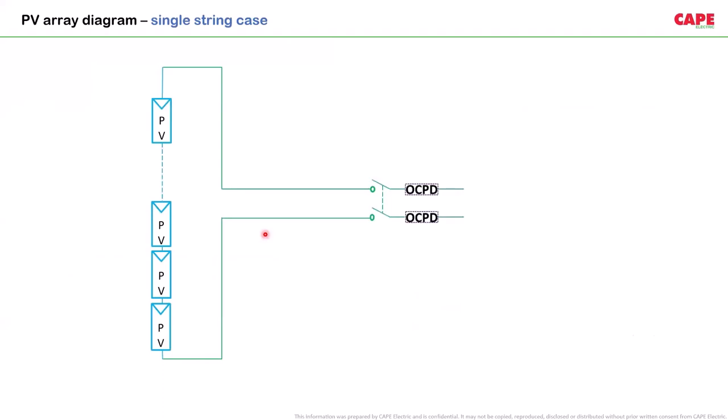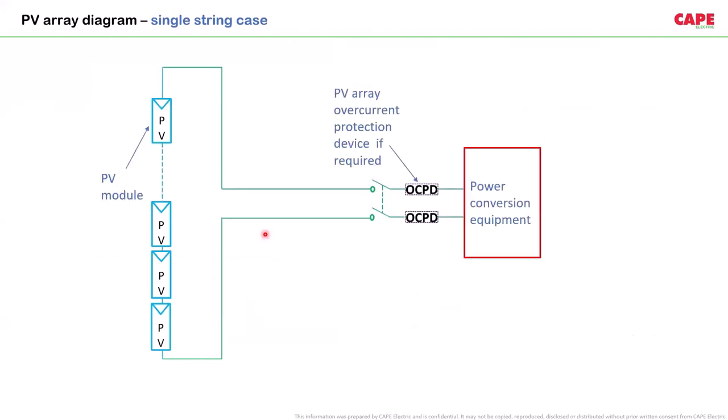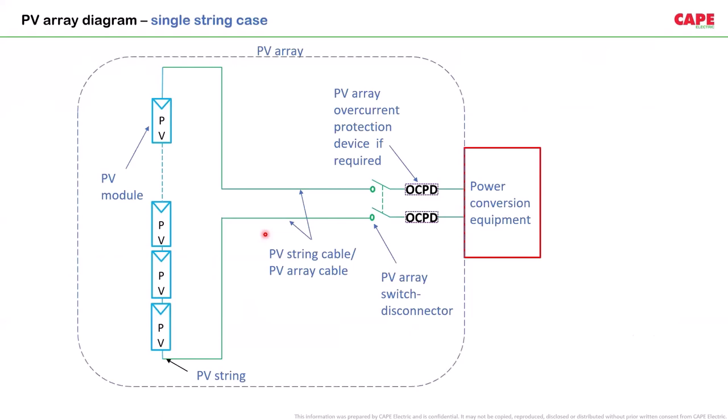Otherwise, if I explain a DC circuit and you think of it in a different way, it becomes very difficult. So the PV array consists of PV modules, sometimes in series combinations in order to attain a certain operating voltage for the purpose of reducing the current. Then the PV string cables are there. There are OCPDs, overcurrent protective devices, isolators, and power conversion equipment.